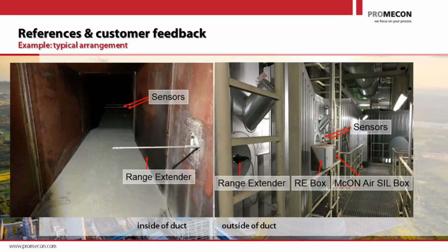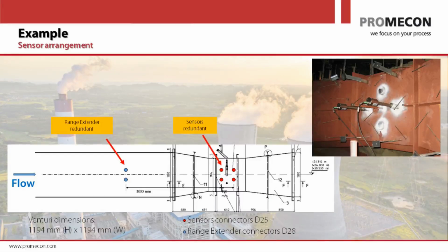So every 2 years they have to do what they call a proof test, and this proof test is basically switching our system off and switching it on again, and that's basically all we do. Then the system checks itself and it comes back online correctly, then everything is fine. So we could say no maintenance actually, only regular checks. That's what we would recommend. If you have a boiler outage, go through all measurements and check if there's any visible damage to the cable, to the sensors. Pull the sensors, they're still looking good. But if they do and the system comes back all right, then you are fine. It's a digital system. There's nothing else to do.